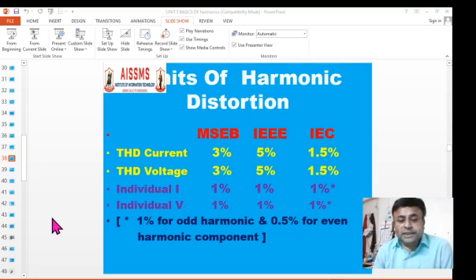In case of IEC, 1% for odd harmonics and 0.5% for even harmonic components are taken into consideration. Coming to voltage, as per the MSEB standard, 1% voltage harmonics is allowed. As per IEC, again 1%, and as per IEEE, again 1%.